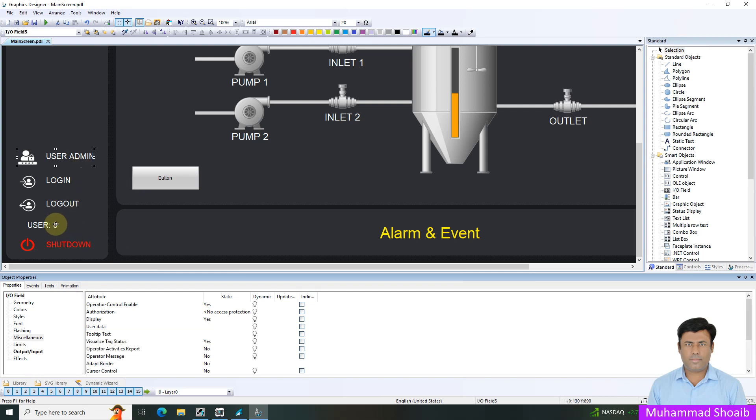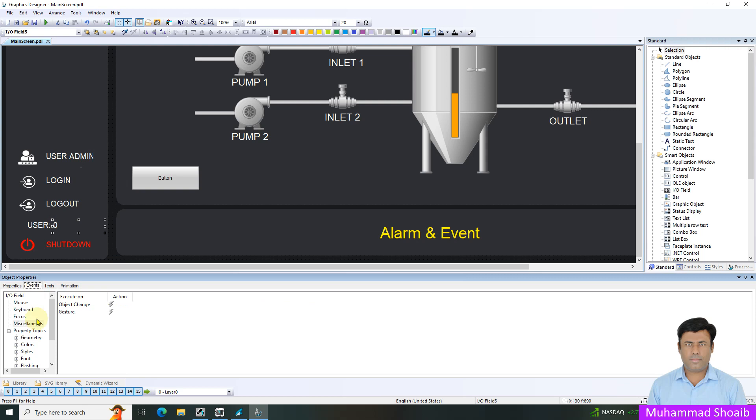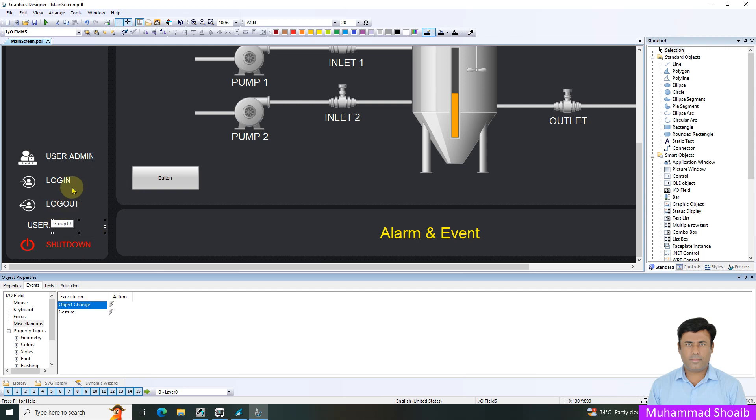The third step, I will come here and add some script. Come to event, miscellaneous, object change. Object change means if any value changes in this text box or object, then this script will execute. I want to execute this script every time because once the user account will change, suppose operator to login, administrator, supervisor, the text will change, so only at that time I want to execute this script.